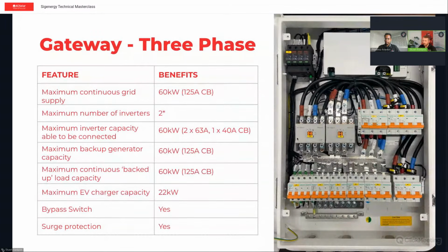Now, I don't have a photo here of the distribution board, but again, a very similar setup. The rating you need to work off for the three-phase gateway is 60 kilowatts. Now, that does mean that with Sigenergy installs, with the 2 currently available gateways, you're limited to 12 kilowatt single-phase systems or 60 kilowatt three-phase systems. Now, there are solutions to go bigger than that, but it's something to keep in mind because there are additional costs when you go above those system sizes. It's really important if you go and quote an 80 kilowatt job, make sure you're across this, you give us a call first because you don't want to get caught out by an extra 5 or 10 grand on that job.